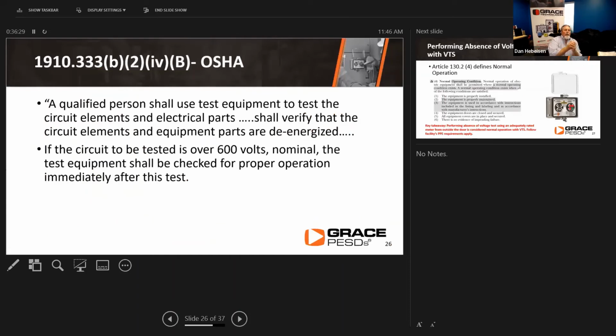Taking a look at OSHA 1910.333, a qualified person shall use the test equipment to test the circuit elements and electrical parts. They shall verify that the circuit elements and equipment parts are de-energized. And if the circuit to be tested is over 600 volts nominal, the test equipment shall be checked for proper operation immediately after the test. So you're going to test your meter, do your process, verify your meter.